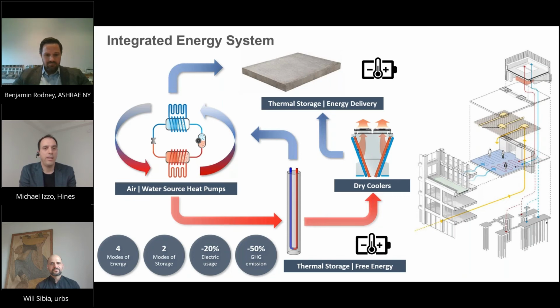So why is this solution so great? I think I tried to capture it in this slide, but for me, it's the integrated approach to it, right? We have 4 modes of energy production. We have air source heat pumps, water source heat pumps. We have the geothermal system. We have dry coolers. So we have 4 modes of operation. We're not beholden to the peak efficiency of that equipment on a peak day. Every piece of equipment can be switched on or off based on the temperature and the climate on any given day. The other is 2 modes of thermal storage. We can store that energy when it's not needed into the radiant slabs or into the piles. So we're able to do that by preloading the slabs, dropping the temperature by 2 degrees.